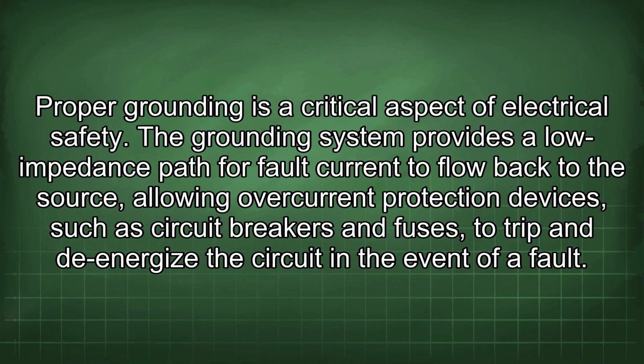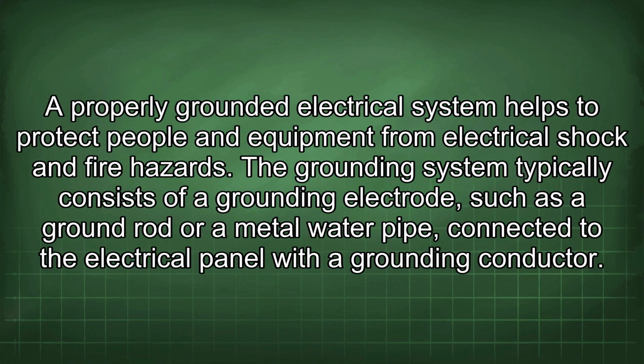Proper grounding is a critical aspect of electrical safety. The grounding system provides a low impedance path for fault current to flow back to the source, allowing overcurrent protection devices, such as circuit breakers and fuses, to trip and de-energize the circuit in the event of a fault. A properly grounded electrical system helps to protect people and equipment from electrical shock and fire hazards.